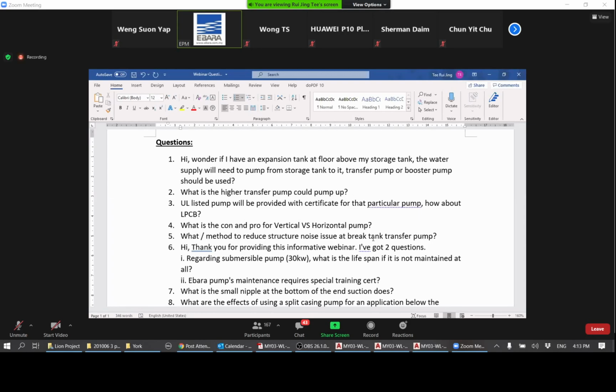What is the highest a transfer pump could pump up? Well, our vertical multi-stage pumps, like I mentioned earlier, can easily go up to 200 meters head, and that's easily, I would say, a 40-50 story building. But in such cases, normally you would use intermediate or rather two-stage pumping, and there are good reasons for that. We will cover that in our next topic on high-rise pumping applications. But to answer your question simply, vertical multi-stage pumps can easily do up to 200 meters head if you need that kind of pressure. Thank you very much. I have nothing else.